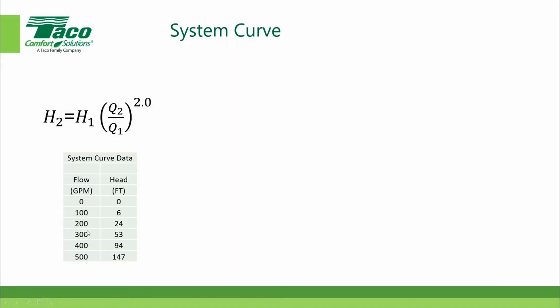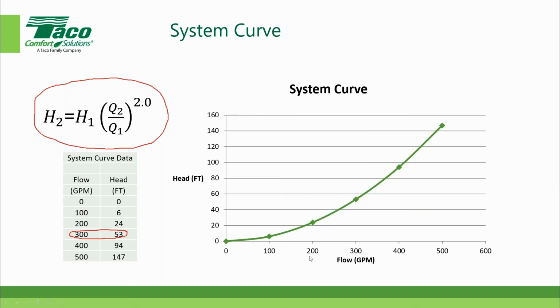So here's our design condition of 300 gallons per minute at 53 feet. Now all I have to do is plug in the different flows, and using this calculation formula up here, I will get the different pressure differentials. And I plot that on a chart, where the x-axis, or the horizontal axis, is flow in gallons per minute, and the y-axis, or the vertical axis, is differential pressure in feet.